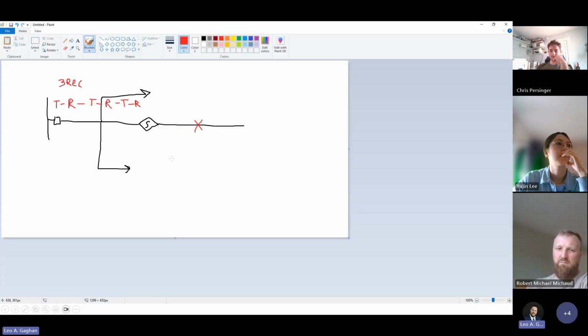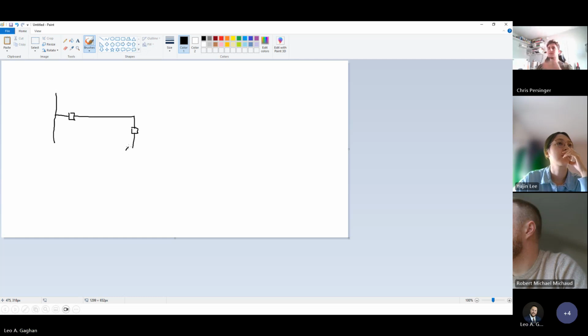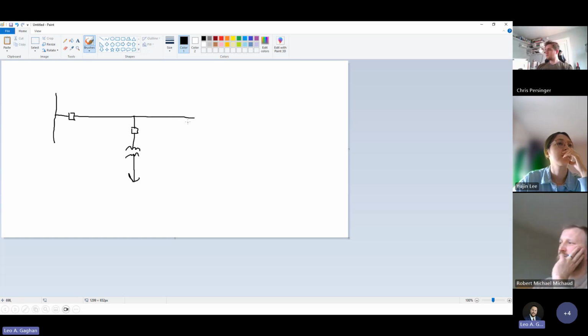I guess what I'm trying to describe there, if it's tough without a visual, is let's say you had a breaker, you're going to go to another breaker. You've got a transformer, and then you can continue down the line, you've got other stuff. So sometimes it would be okay to have an instantaneous element that overreaches another device if that device does not have reclosing. So if the upstream device does have reclosing.